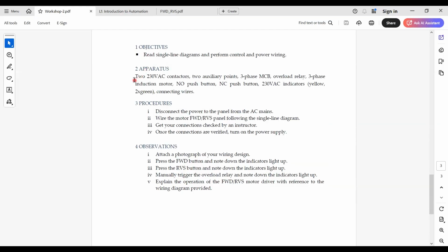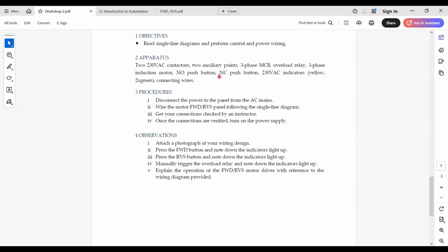For this workshop, you need to have 230-volt contactors and 2 auxiliary points, which are going to be mounted on top of these contactors, because some contactors do not carry sufficient contact points. So we have to plug auxiliary contact points on top of the contactors. And a 3-phase main circuit breaker, overload relay, 3-phase induction motor, normally open and normally closed push buttons, and light indicators, basically yellow and 2 green lamps and 1 red lamp if required for indication purpose.